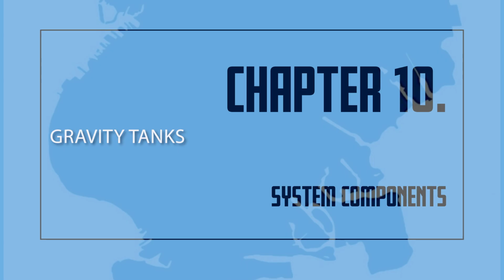The gravity tank is extremely reliable. It does not depend on the operation of mechanical equipment to supply the sprinkler system. Automatic fill pumps supply the water to most gravity tanks. The pumps fill the tank at a rate of 65 gallons per minute or more. The floats turn on the fill pump when the water in the tank is too low. The floats shut off the pump when the desired water level is reached. The floats make sure the gravity tank always has the right amount of water to supply the sprinkler system.